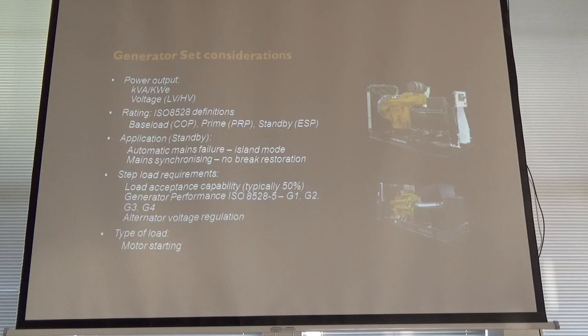Often when they churn them out in the factories, you'll either be able to just put an input on the control panel, whether it's a standby or prime rating, you just put the parameters in. So in other words, you can't tell the difference between the two, and you can easily plug in one or the other with those. The different one is the COP. COP stands for Continuous Operating Performance.